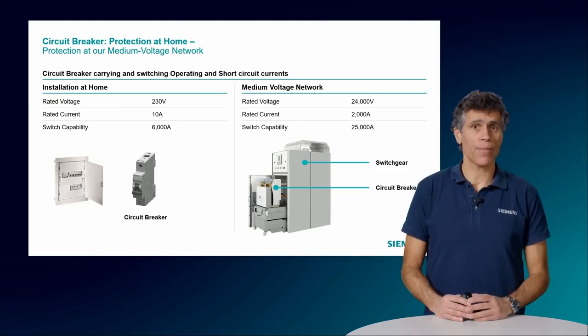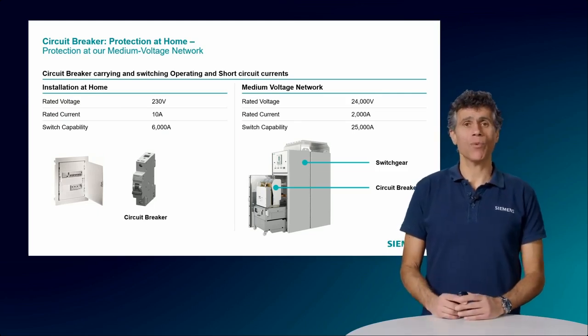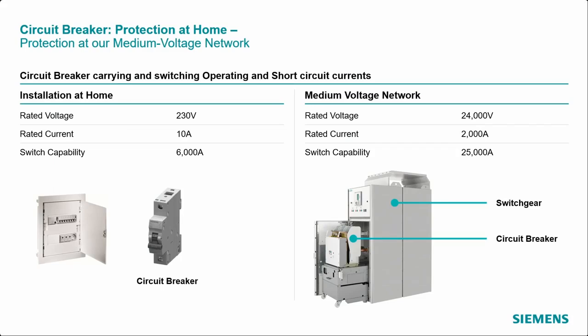conditions, as said before. On the other hand, in medium voltage networks, an outgoing panel may feed the equivalent to 10 or 20,000 homes. The amount of energy is much higher, and so are the demands to the circuit breaker on that level. A typical circuit breaker on a rated voltage of 24,000 volts has a rated current of 2000 amps and a switch capability of 25,000 amps. This specification highlights the robust requirements needed to handle not only the higher operation loads, but also the much more severe fault conditions in high voltage networks.